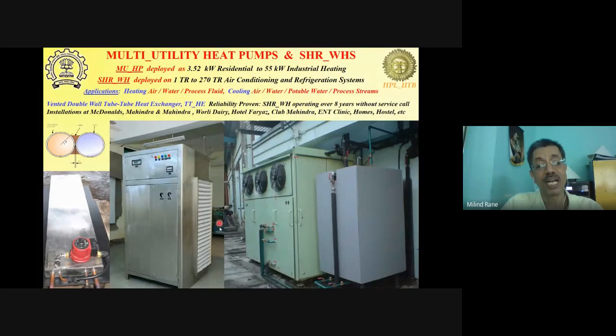As the shop floor was not originally air conditioned, the management was not ready to give us credit for the saving because of the air conditioning. So we said that, okay, we'll generate some chilled water, and that chilled water was then supplied into the water coolers. So the compressors for the potable water coolers were no longer required to be operated. Thus, this 3-in-1 heat pump has been operating, and as far as I know, they were operating for more than 8 to 10 years in the industrial environment.